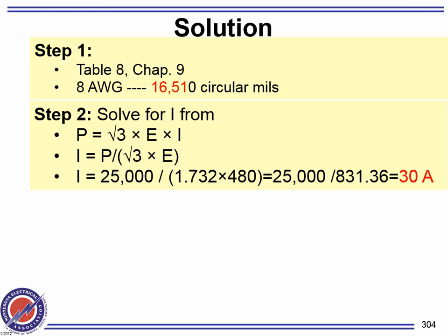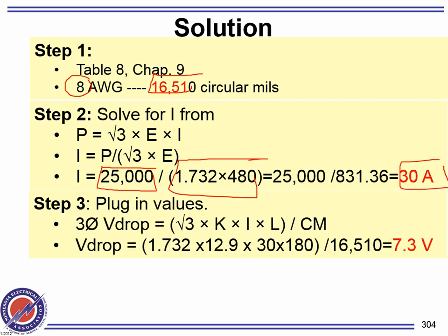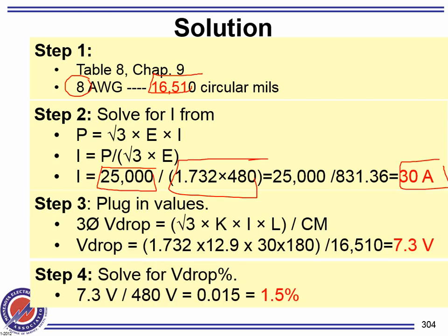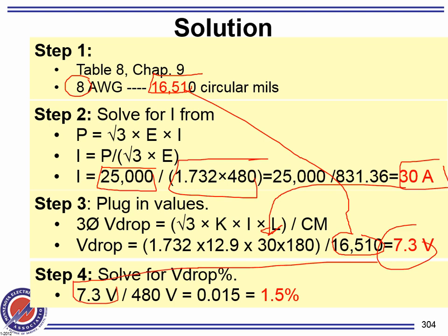Okay, well, here's the number 8. Here you need the circular mil for it, which is easy. Then take the kVA. Here's the kW, divided by the voltage and 1.732. That'll get you 30 amps. You have to find the amps first. Okay. Once we get the amps, you plug them in. Here's your amps coming in here. Here's the circular mil coming in right in here. The rest of it is K over CM. 1.732 K over CM. And that'll get you 7.3. Is it good, bad, or ugly? You don't know. So how do you know? Divide the drop over the voltage, and that will get you what? 1.5, 1.5%.